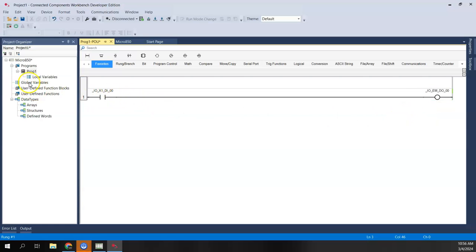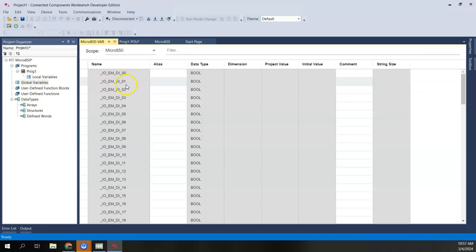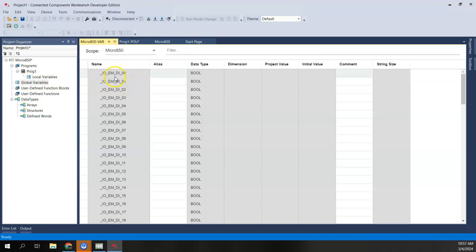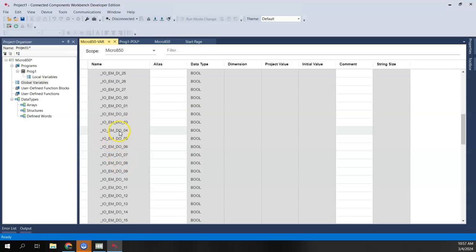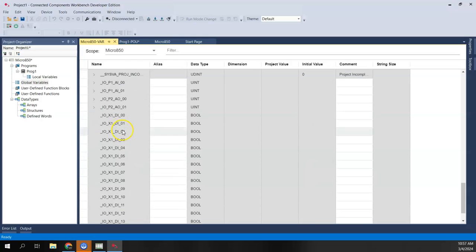If I look at my global variables: EMDI are the embedded discrete inputs, EMDO are the embedded discrete outputs, P1 and P2 are plug-in one and plug-in two, and IOX1 is expansion card one. Since that expansion card is a digital input, it's labeled DI. So we have analog in, analog out, and digital in for expansion cards.